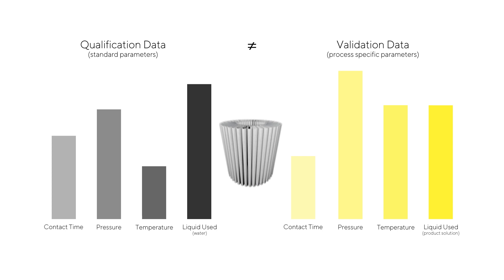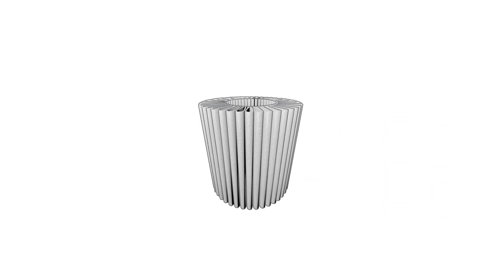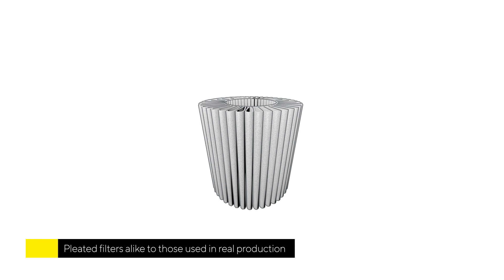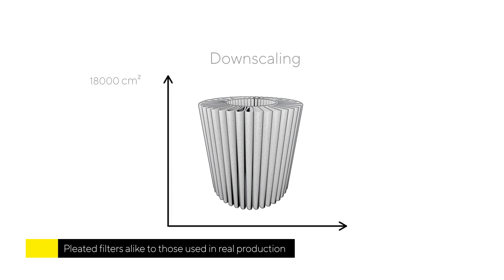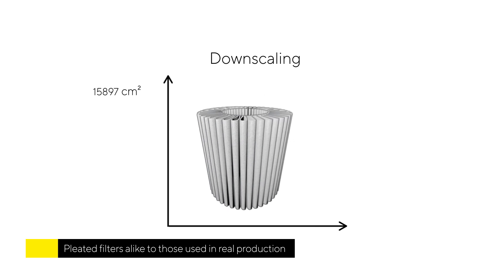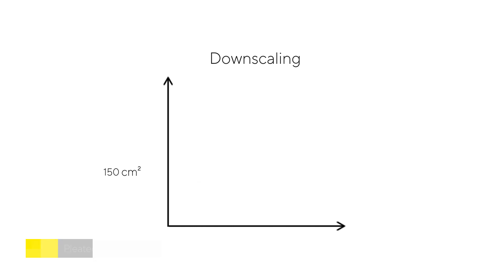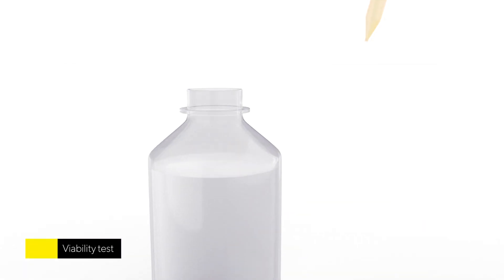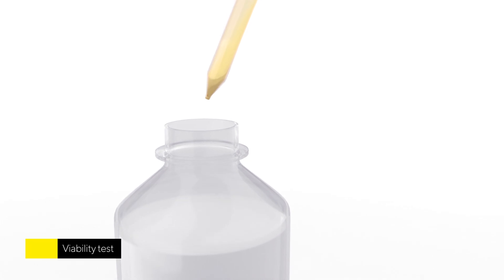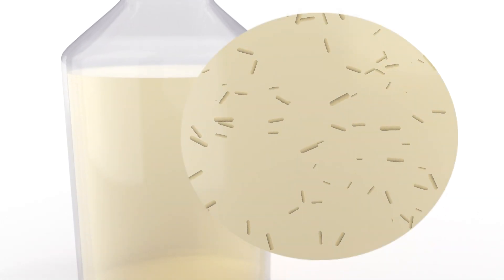For a BCT, Sartorius successfully uses pleated filter devices that are alike to the filters used in real production at customer site to transfer pharmaceutical processes into laboratory conditions. To select the optimal approach before the BCT, a viability test is performed. It establishes whether the test fluid affects the viability of the test organism.